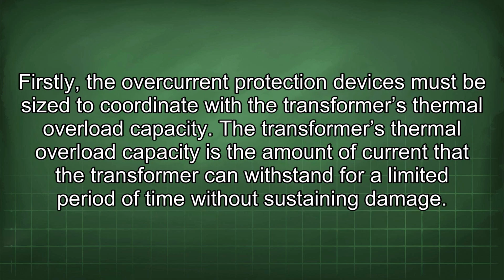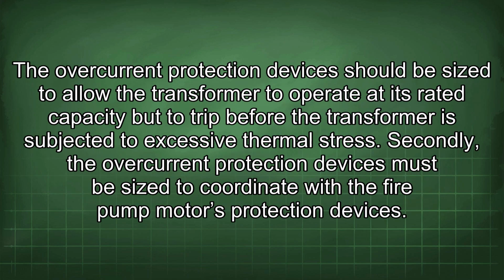Firstly, the overcurrent protection devices must be sized to coordinate with the transformer's thermal overload capacity. The transformer's thermal overload capacity is the amount of current that the transformer can withstand for a limited period of time without sustaining damage. The overcurrent protection devices should be sized to allow the transformer to operate at its rated capacity but to trip before the transformer is subjected to excessive thermal stress.